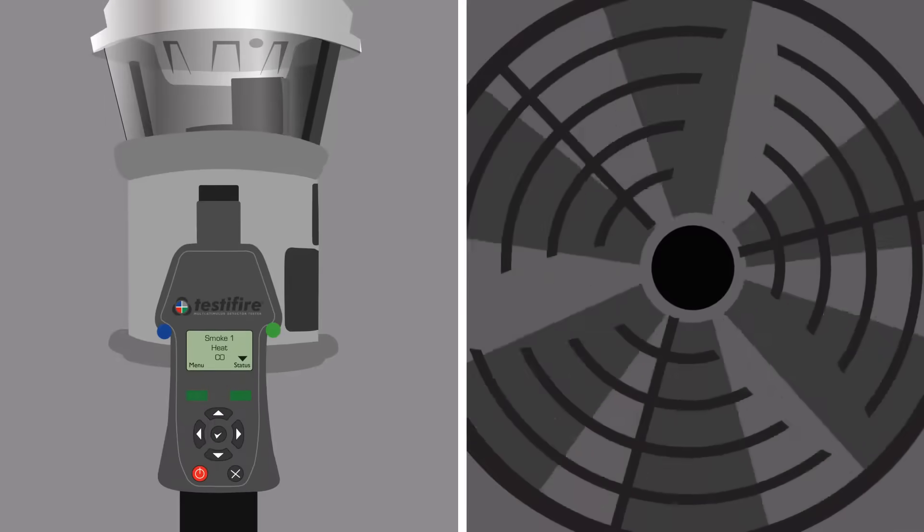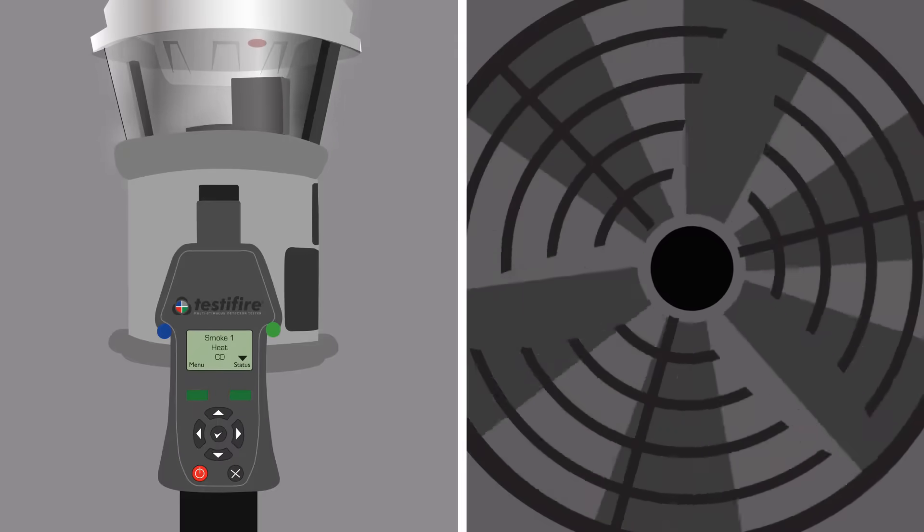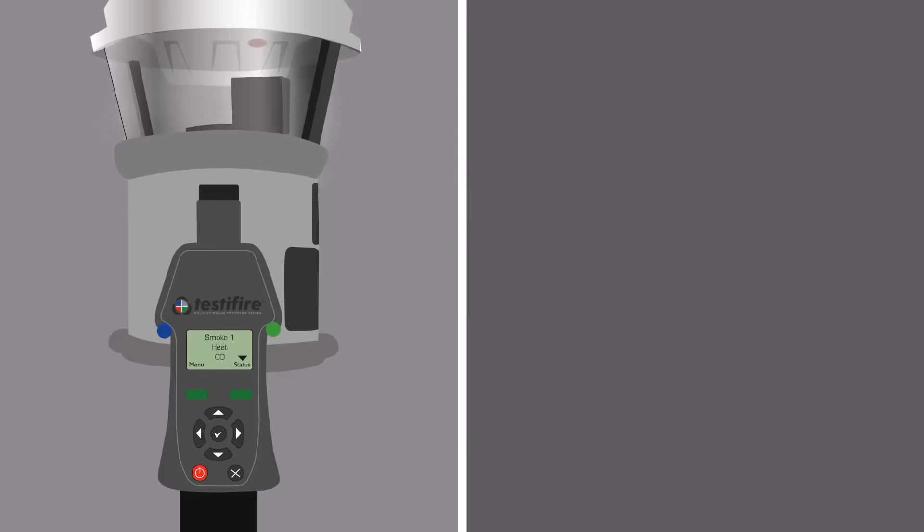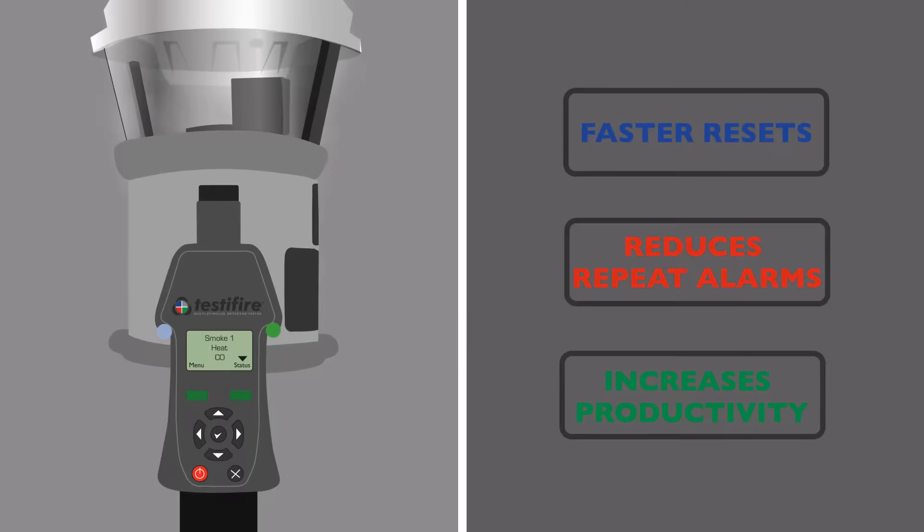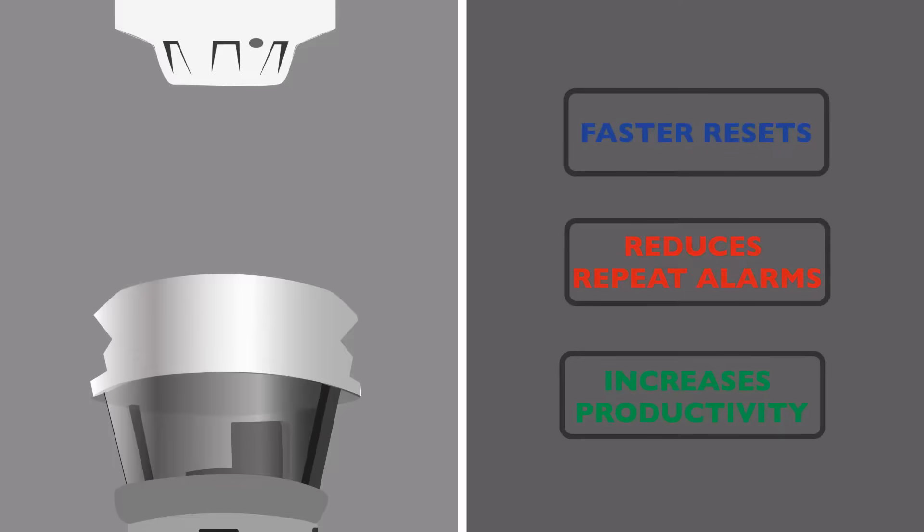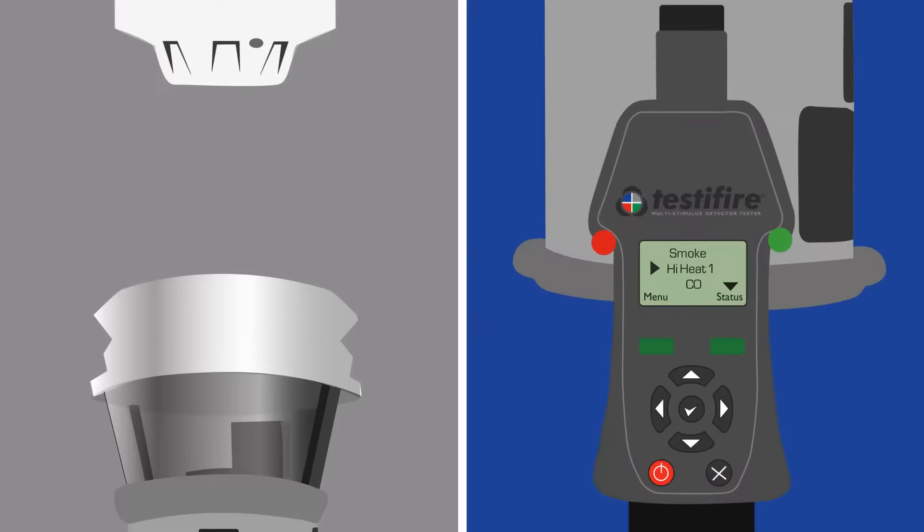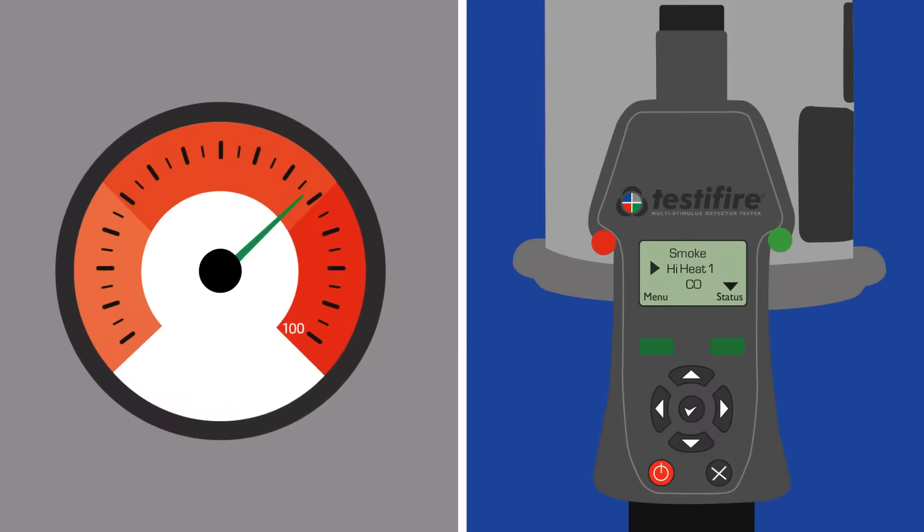And that's not all. Users tell us that the clearing function and the high heat setting are real advantages. The clearing function blows smoke away from the detector, preventing repeat alarms and saving significant time on site. The high heat settings allow for testing of heat detectors that require a temperature higher than 90 degrees Celsius to activate.